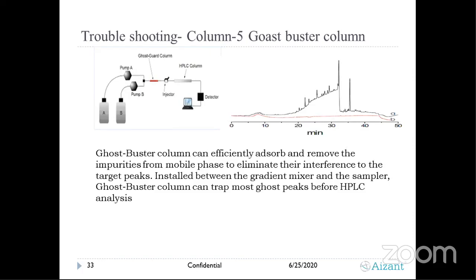And you can see in the chromatogram how the baseline is without the Ghostbuster column, and with its use how it has been smoothened. This is the upcoming technology, and these columns are provided with patents. There are 3 or 4 suppliers in the industry which provide this Ghostbuster column, but the packing and other components they are not disclosing. But the phenomenon is through adsorption or some ion exchange on metallic impurities or very specific impurities with respect to the solvent, which they are taking care of.